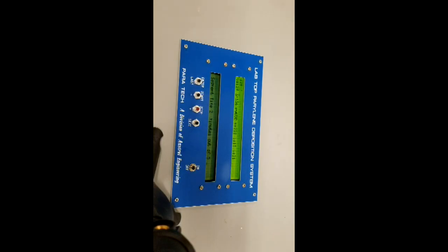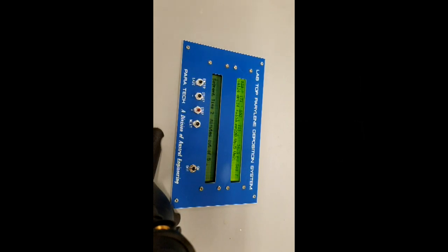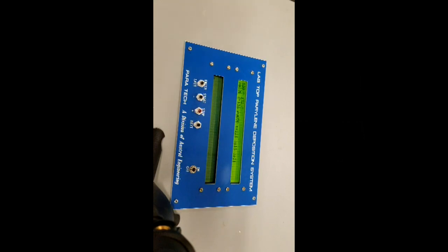Okay, here we're in segment 7. We're ramping up to the 130 degrees for the vaporizer. Just one thing to point out, in order for the process to end properly, the vacuum has to go above 21 microns, which would happen if you had dimer in there vaporizing and the pressure would go up. So I'm going to have to simulate that by opening the vent valve when we're near the end of segment 8. So we'll come back then and simulate a vaporization and end of process.